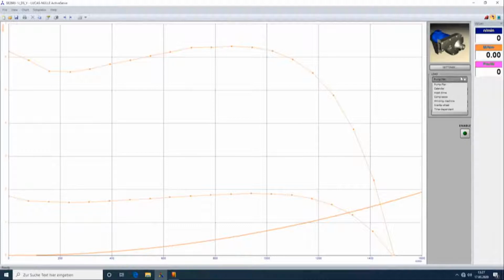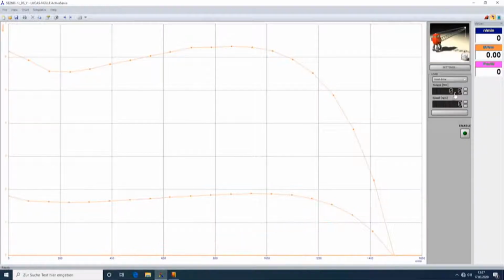I will move to another working machine like a hoist drive, which could be a normal tooling machine in the industry. If I look on the motor nameplate, I see this motor has a value of approximately 0.37 kilowatt, so the torque should be around 2 and something Newton meters. So I applied a value of 2.2 Newton meter for the torque.